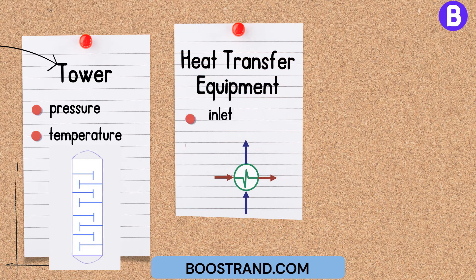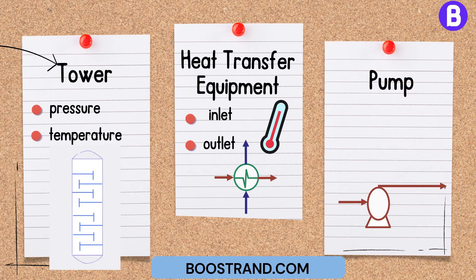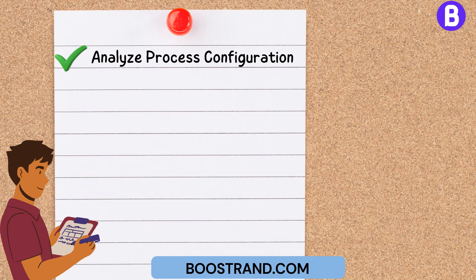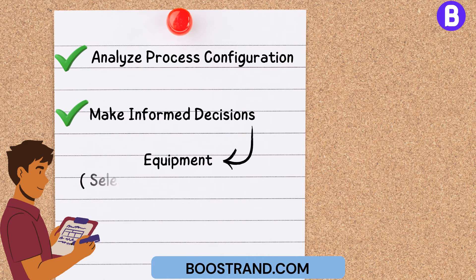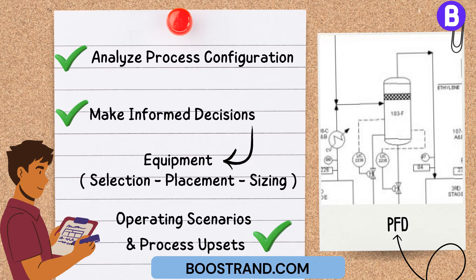For example, if we are dealing with a tower, a PFD typically shows the operating pressure and temperature of the top and bottom sections. For heat transfer equipment, we show the inlet and outlet temperatures, and for a pump, we sometimes show the volumetric flow rate. This visual representation allows engineers to analyze the overall process configuration and make informed decisions regarding equipment selection, placement, and sizing, as well as evaluate expected operating scenarios and process upsets.